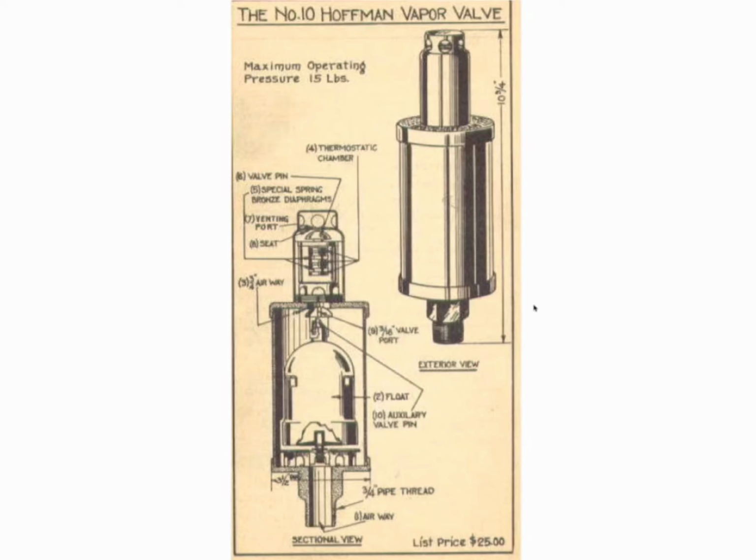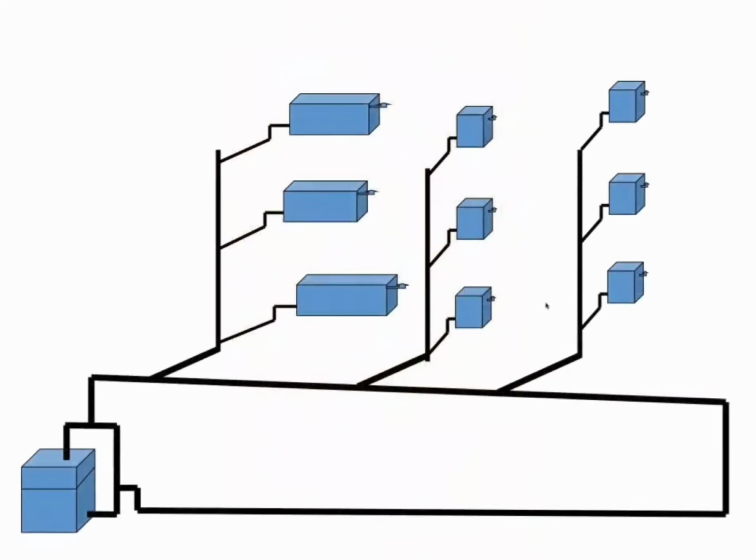And this was developed during the time when we began to move away from coal and toward the automatic fuels of oil first and then natural gas afterwards. Because those automatic fuels change things dramatically. Here's what I mean. When you start up a boiler, the steam's going to form. We're going to have an air vent down the end here, and they might put that Hoffman number 10 down there. And when the steam starts up, we want this to happen. We want the steam to move through the header.